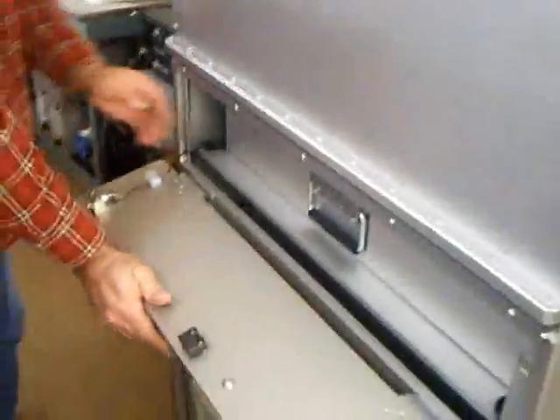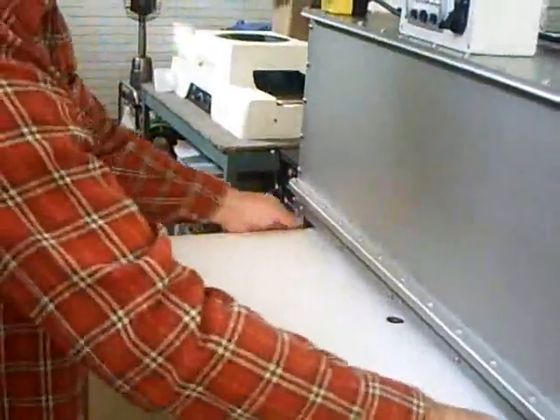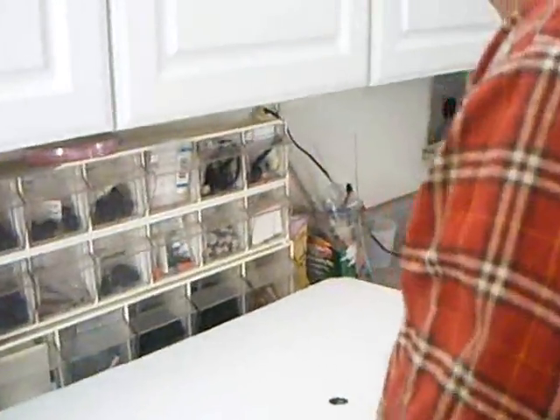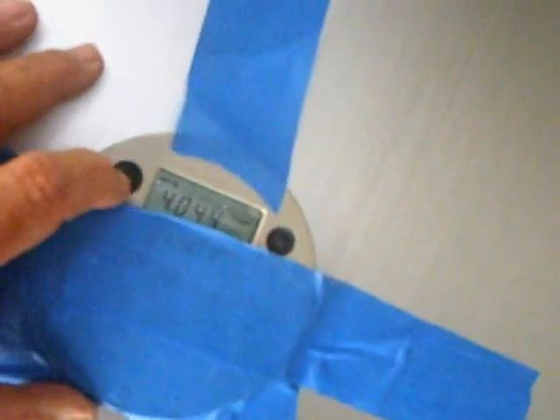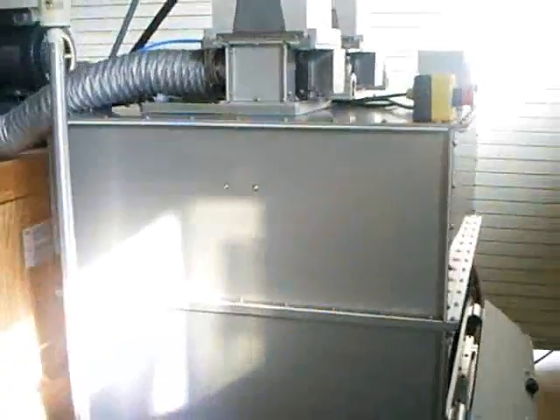Okay, so now we've got to take the fixture out, and let's see how close to 4 joules we were able to get. And we're in the run mode here. There we are. Hopefully you can see that: 4.044 joules. So we're within 44 thousandths of a joule of being right on the preset point. And there it is, the first one for our R&D.